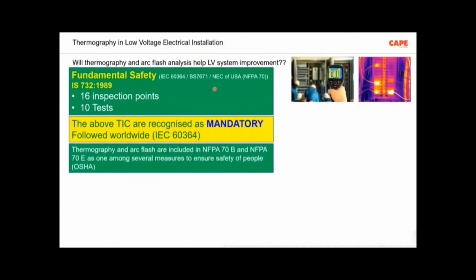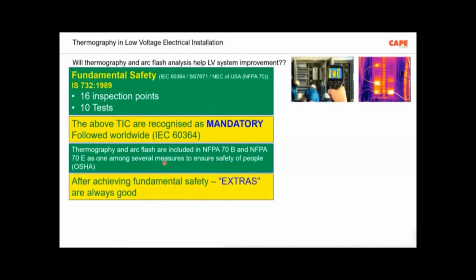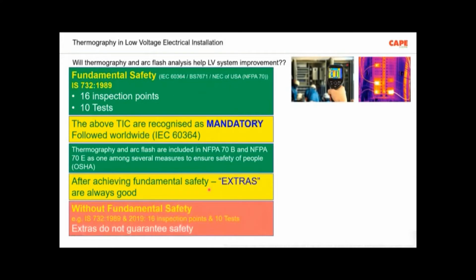Now, in the American standards NFPA 70B and 70E, for OSHA or to comply with other enhanced, additional safety measures, or let us say extras, thermography and arc flash studies are considered one among several measures. Please understand, one among several measures. Thermography is not the only one. Arc flash study is not the only one. But fundamentally, you have to have this 16 plus 10, which is mandatory. The additional things, thermography and arc flash, are extras. After achieving fundamental safety, extras are always good. Extra tests ensure additional safety for you.